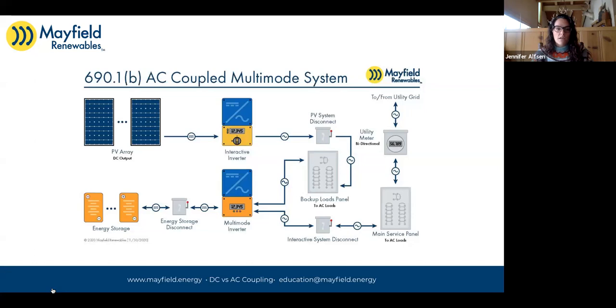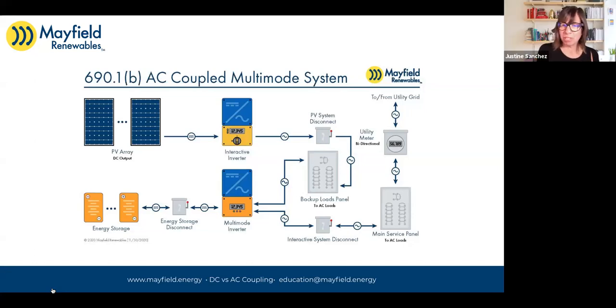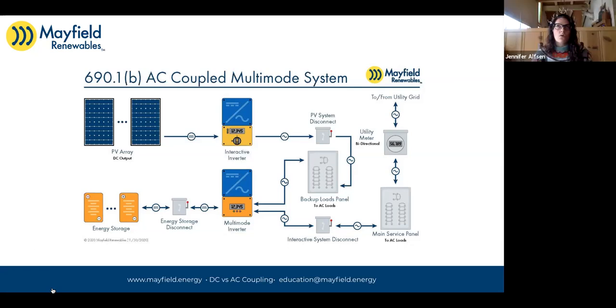An AC coupled system with only a multi-mode inverter? So to answer - no, it's going to have two inverters. AC coupled means the PV inverter, or the interactive inverter, converts the energy coming from the solar system first, and then you attach it to an energy storage system. That's why two inverters are required there.